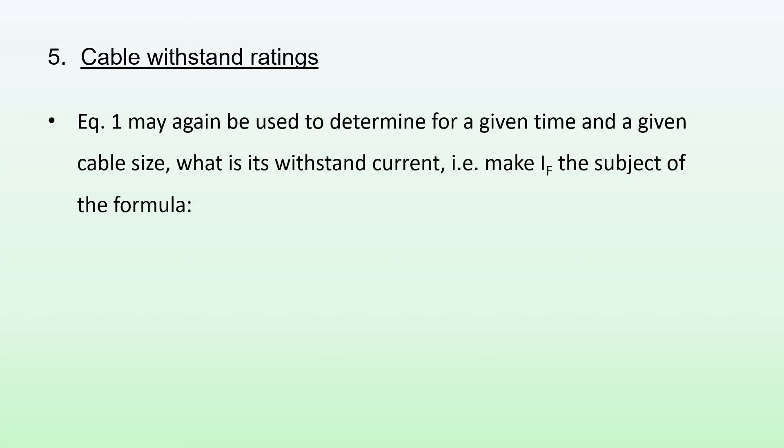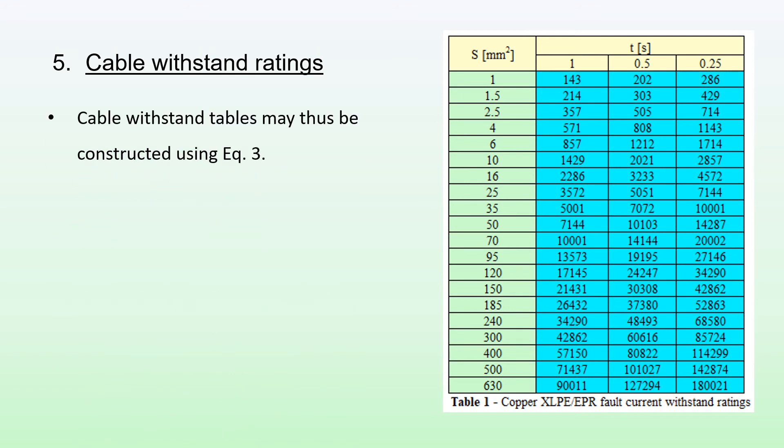Now let's look at cable withstand ratings. Equation 1 may again be used to determine for a given time and given cable size what is its withstand current. We make the fault current the subject of the formula, so we have equation 3. We can construct the withstand table by using this equation 3. For various different times, here I've used 1, 0.5, and 0.25 seconds, and for all the various cable sizes I've determined what are the withstand currents for these various cable sizes for a given time.